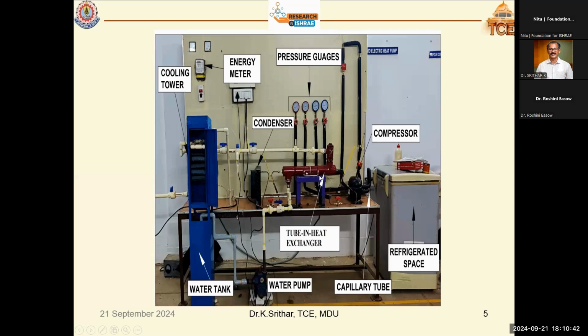So you have a heat exchanger. The red color is the heat exchanger, where inside you have the refrigerant tube, which passes directly to this condenser. Outside the heat exchanger, we have a water cooling effect. This water is pumped by means of a pump at the bottom. So here you have a water pump. This water is circulated through the heat exchanger, absorbs heat from the refrigerant, and is again sprayed at the top level here. At the same time, we pass cold air through this pipe, moving from bottom to top. So simultaneously, water is passing from top to bottom, and air is passing from bottom to top.